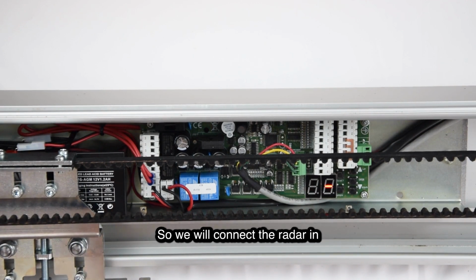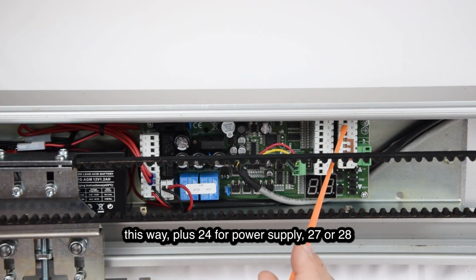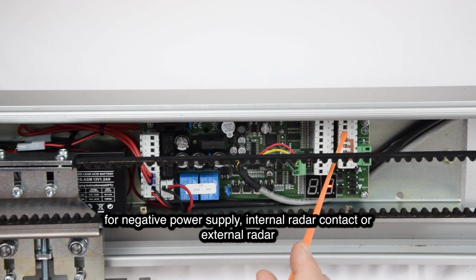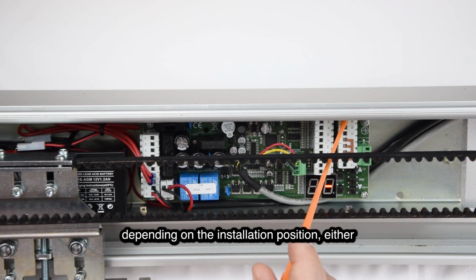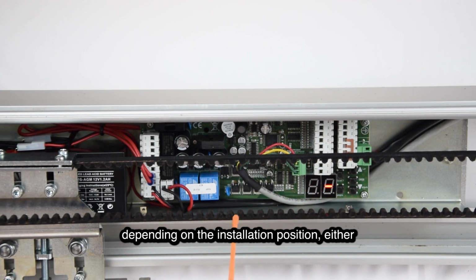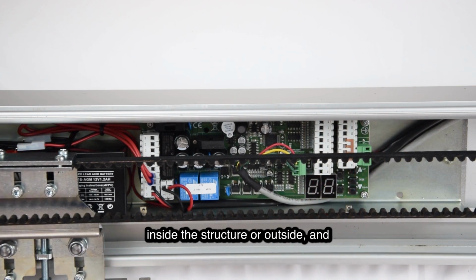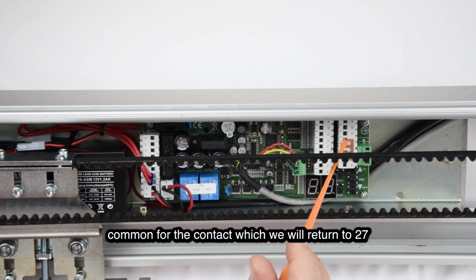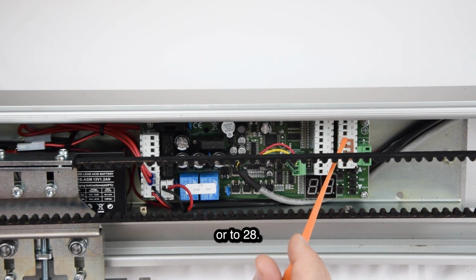So we will connect the radar in this way: plus 24 for power supply, 27 or 28 for negative power supply, internal radar contact or external radar contact, depending on the installation position, either inside the structure or outside, and common for the contact, which we will return to 27 or to 28.